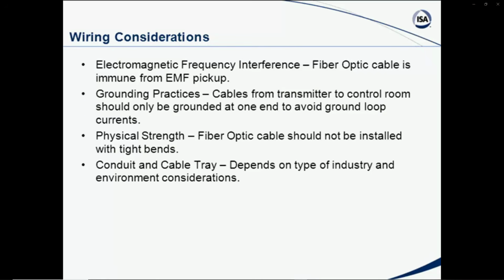But general wiring characteristics, for instance, just a few that I thought of that there's always a chance about, like fiber optic cable is very immune from electromagnetic pickup and all. So it's a very good use for that cable where you have areas with a lot of interference that might be involved. Grounding practices. Grounding is very important not only for certain transmitters that we'll talk about later, like magnetic flow transmitters, but also in the cables running back and forth, perhaps from the transmitter to junction boxes or to other marshalling panels and on into the control room.